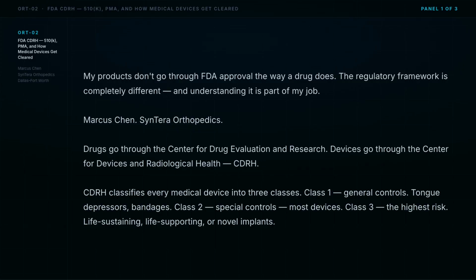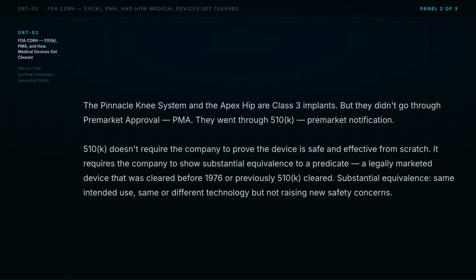CDRH classifies every medical device into 3 classes. Class I, general controls: tongue depressors, bandages. Class II, special controls: most devices. Class III, the highest risk: life-sustaining, life-supporting, or novel implants. The Pinnacle knee system and the Apex hip are Class III implants, but they didn't go through pre-market approval, PMA. They went through 510K pre-market notification.